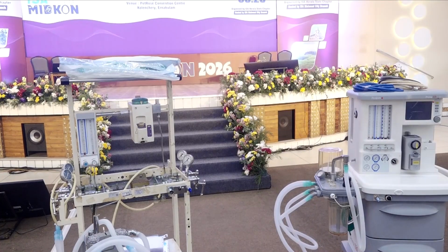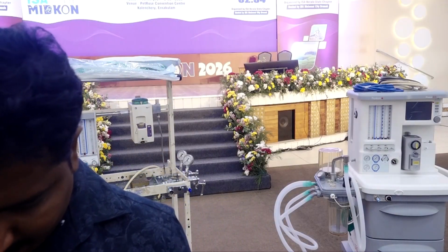But there are problems that can occur, because I was telling you there are two problems. One is barotrauma. Unnecessarily if you just compress it, suddenly so much high pressure gas goes to the patient, and if you have connected an endotracheal tube, it can definitely produce barotrauma. And second thing is, because it is bypassing the vaporizers, the patient becomes light because no anesthetic agent can go. So these are the two problems with oxygen flush.